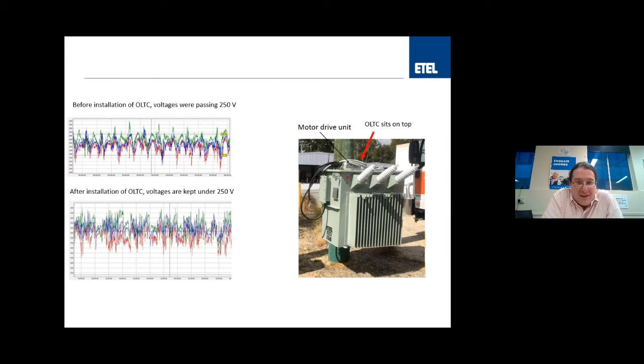The figures on the left show before the transformer was put up, and they're starting to see these green spikes up to almost 256 volts. That's what causes people's PV to trip off - it can no longer export, and these people will not be happy. When we put this transformer on, these voltages were kept below 250 volts, preventing customer outages and ensuring the maximum amount of PV could be exported to the grid.